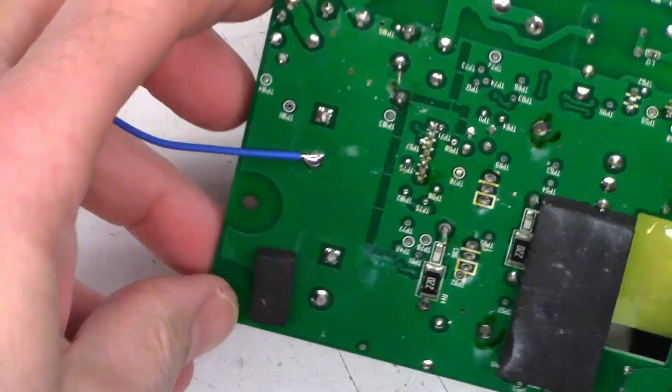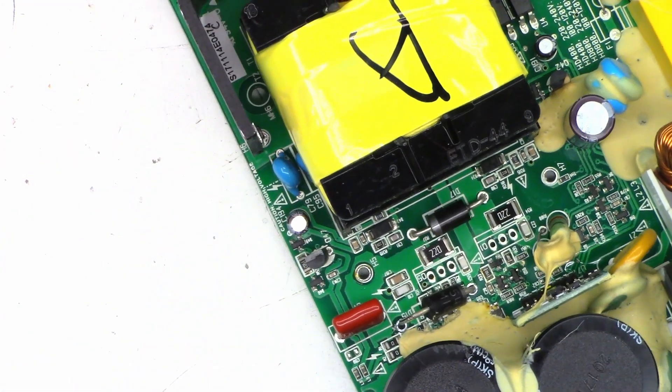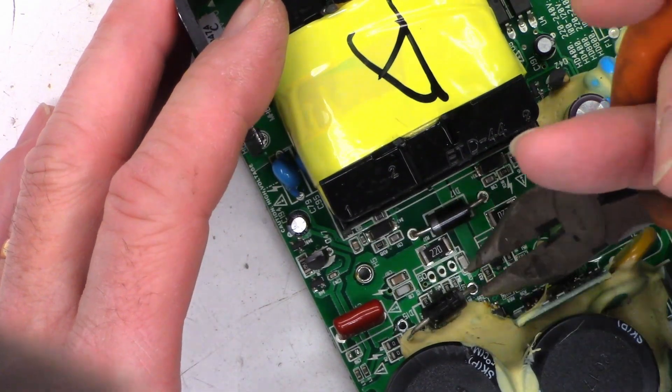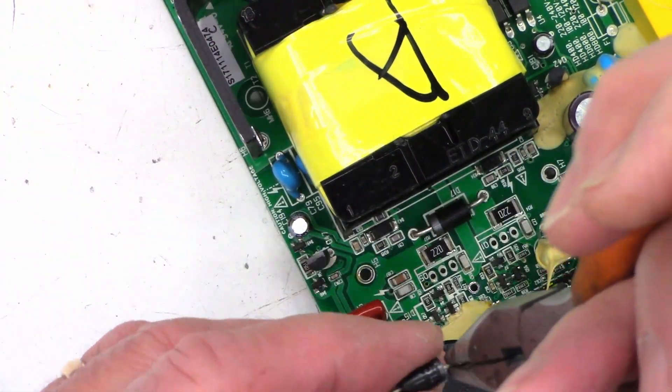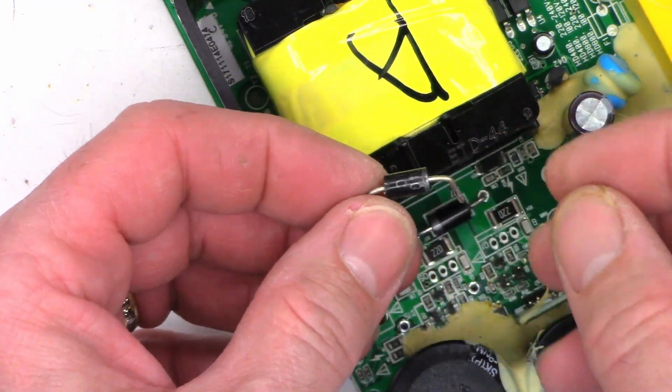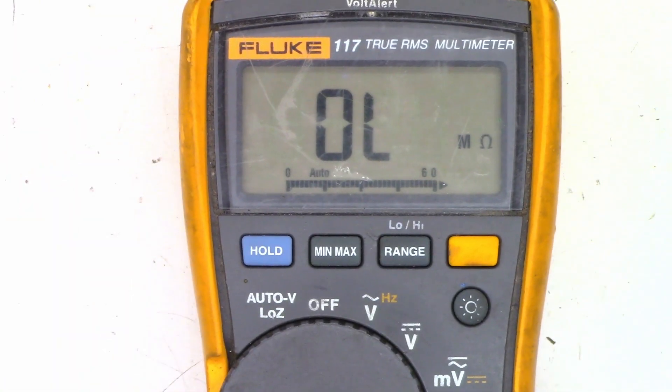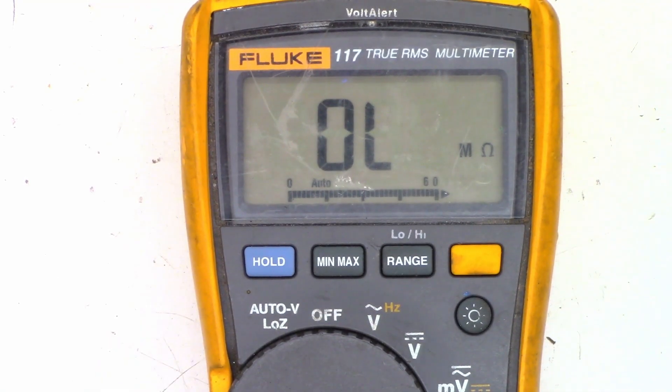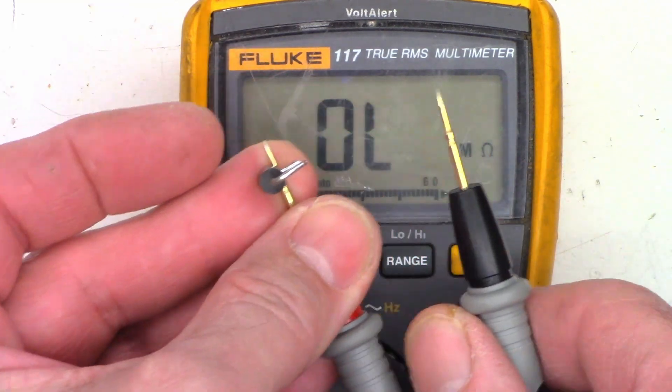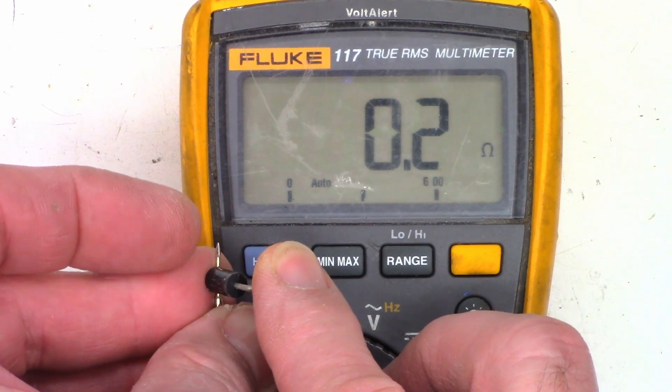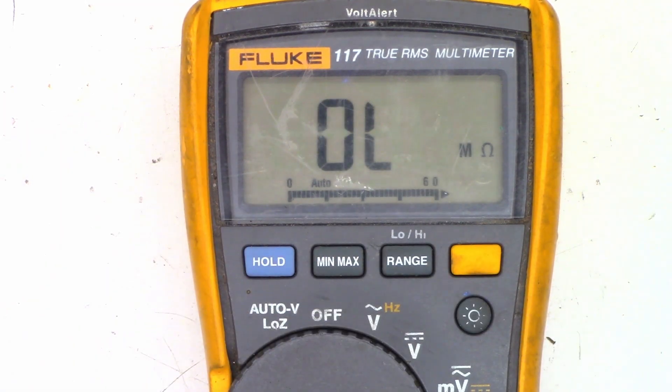Ah, it's stuck. Still a little tiny bit warm. Okay, get the voltmeter or the ohmmeter back into view here. There we go. So I am on ohms. I just want to see if this thing out of the circuit is actually shorted or not. That's a big 10-4, good buddy. It is a dead short.